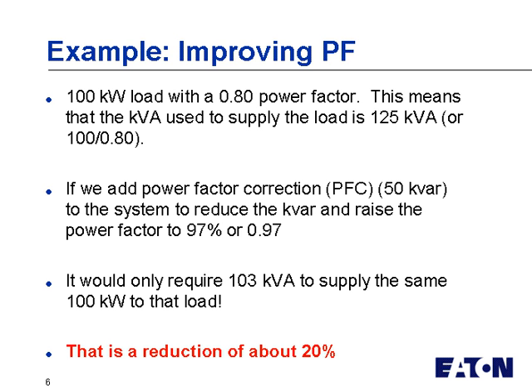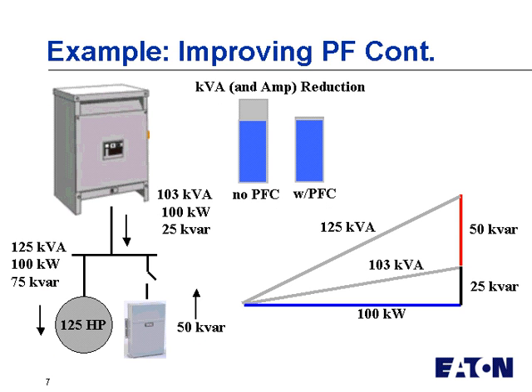So again, for this 100 kW load, 100 kW has to come from a generating source. But again, the kVAR can come locally from some capacitor, for example. And that's a reduction of about 20%, so that can be significant. Now, a lot of people, like myself, like to see things visually with a picture, so this shows that same example with a picture.